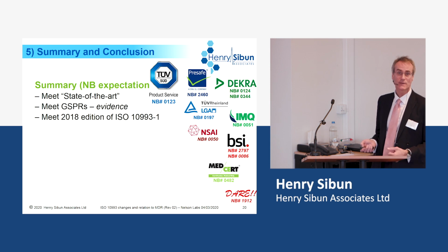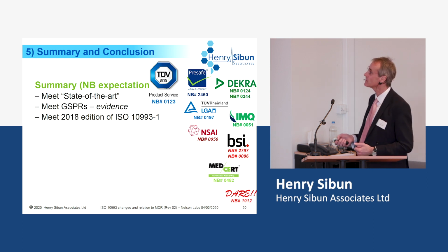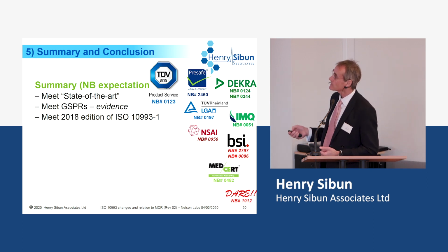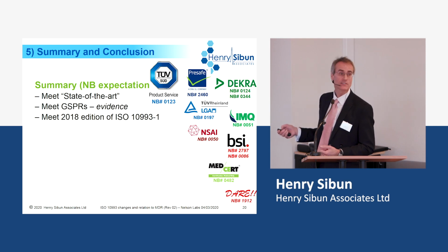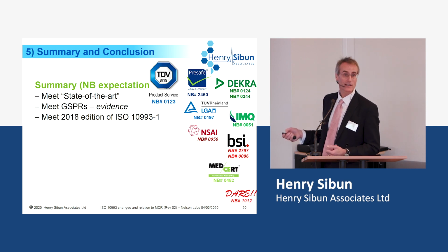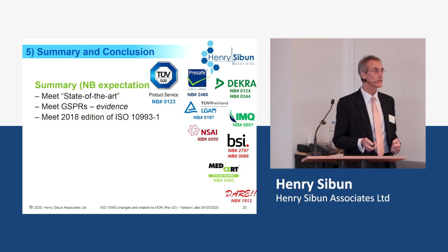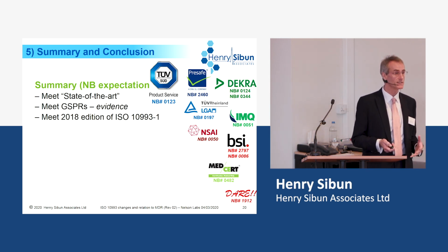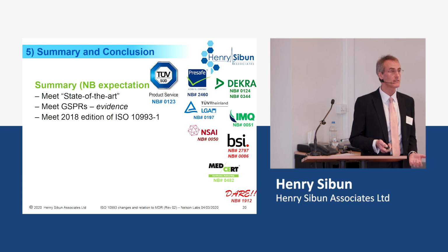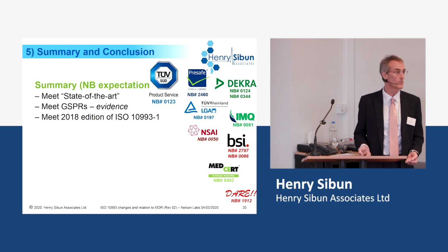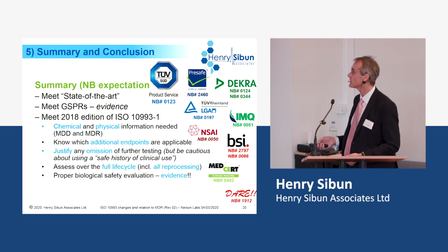You're expected to meet for the MDR state of the art, meet the GSPRs, and actually have evidence for this. We'd also expect you to comply with the 2018 version of the standard. If you're working with the previous version, for the MDD, that's acceptable. For the MDR, it's not. Okay, so you do need to make sure you meet these before you apply for MDR certification.